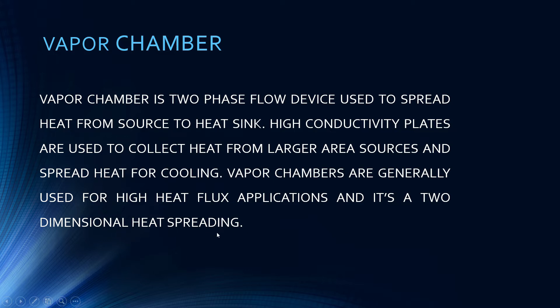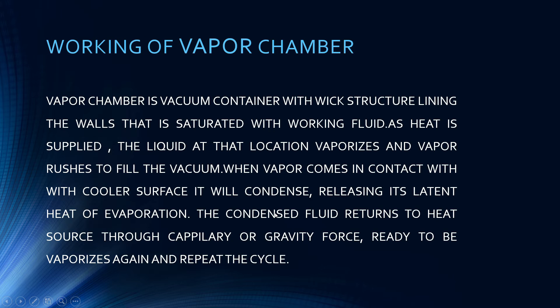The second reason is two-dimensional heat spreading. As you know, with a standard heat pipe, heat transfer is only along the axis of the pipe, and heat pipes are suited to cool discrete heat sources. But in the vapor chamber there is two-dimensional heat spreading, which improves the overall heat spreading performance.